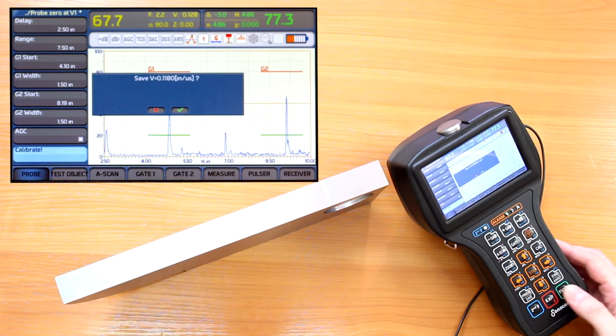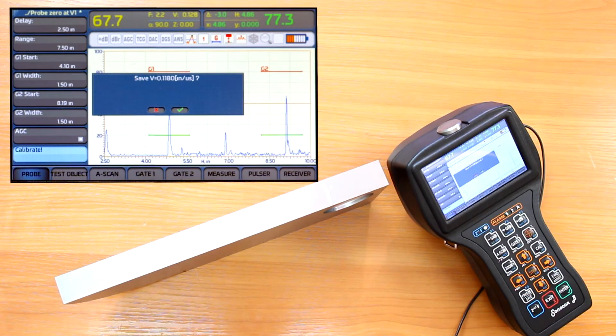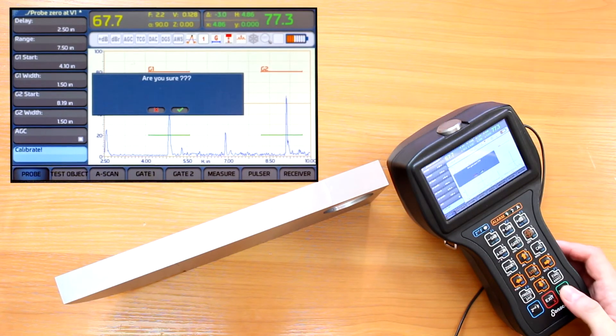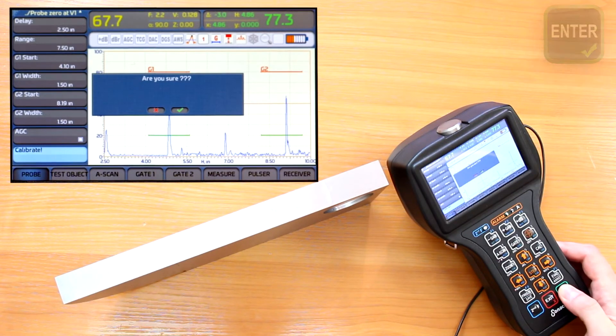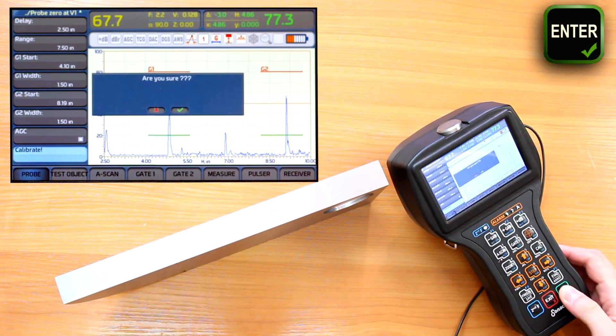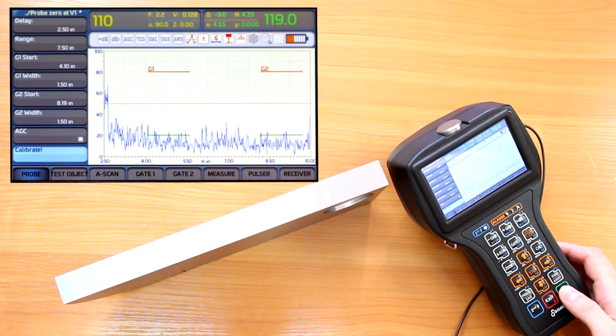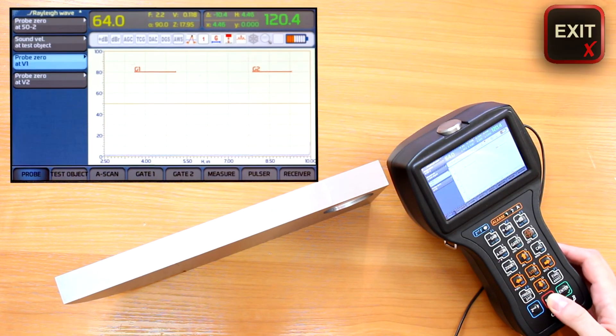It then asks if we wish to save the calibrated value of sound velocity. If we used a V1 made from the same material as the test piece, it's a good idea to save this velocity by pressing enter and confirming again. The same question is asked about the probe zero value, so we press enter twice to confirm it as well. The exit button gets us back from the calibration menu.